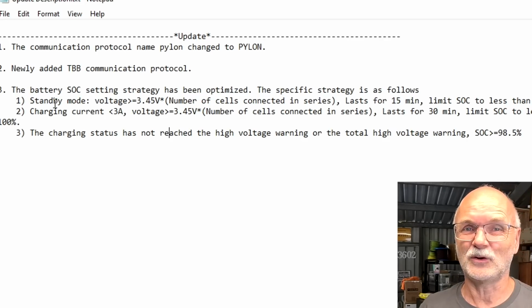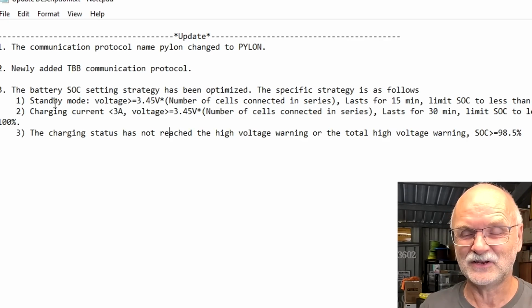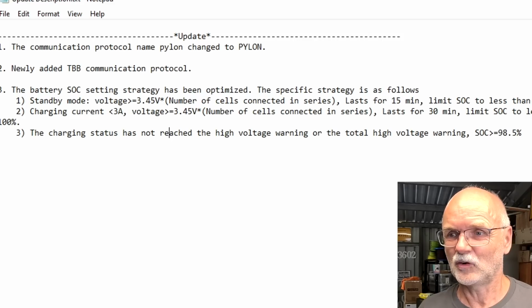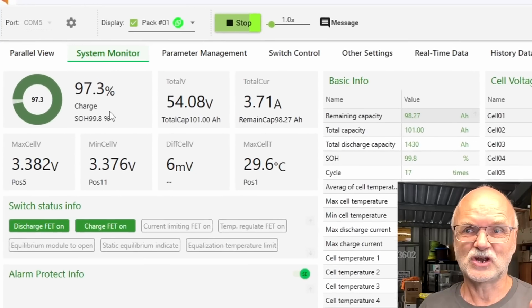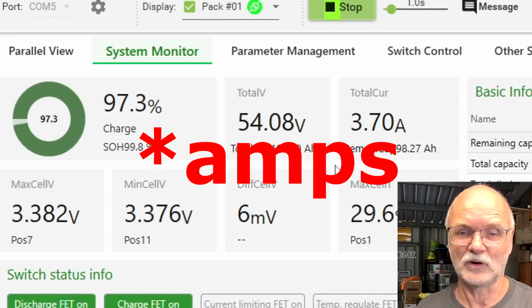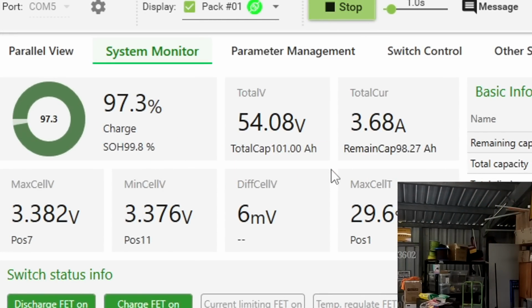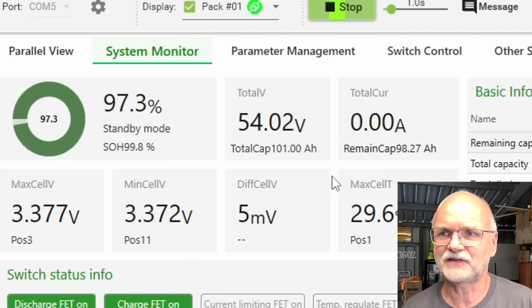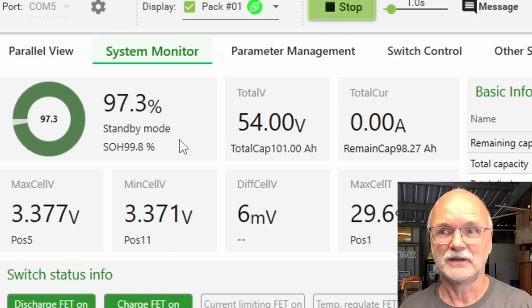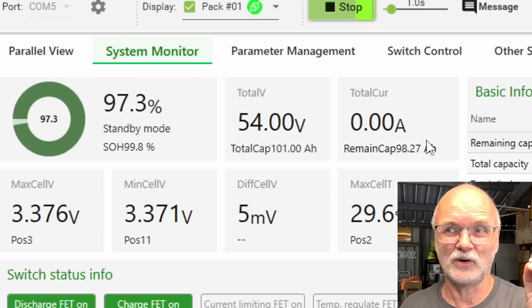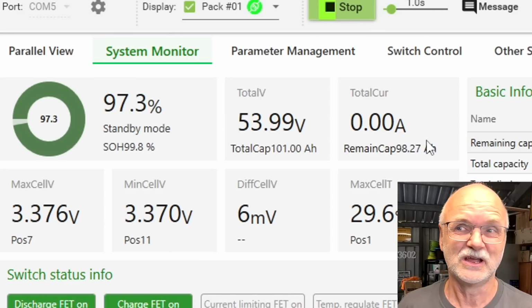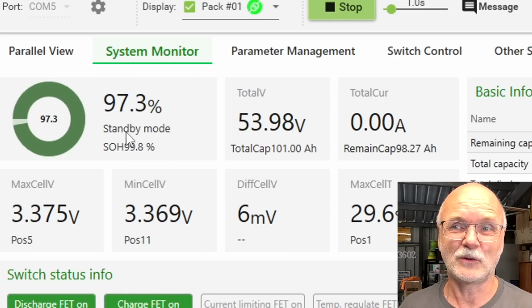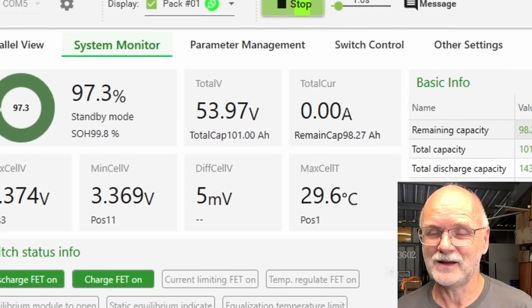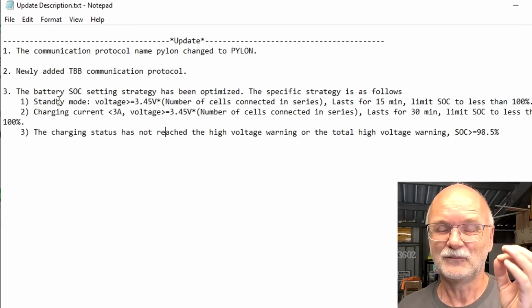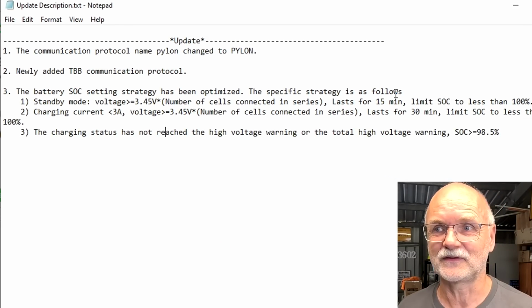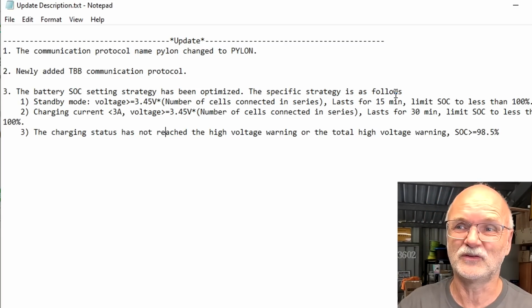The first case here is standby mode. That means there cannot be any charge or discharge current at all. If we go back into the software, it says we're charging now with 3.7 amps. If I turn off the charger for a second, just flick the circuit breaker of the solar, you can see 0 amps now, and we're on standby mode. But as soon as we charge with more than 0.3 amps or discharge with more than 0.3 amps, we're not in standby mode anymore. This is one of the requirements for case number 1: we need to be in standby mode for 15 minutes, so there can be no charge or discharge going into the battery.